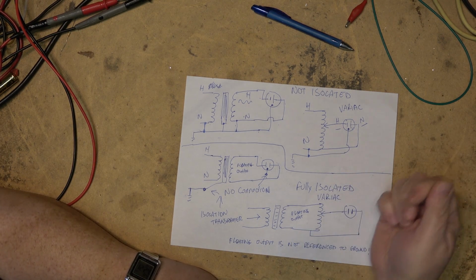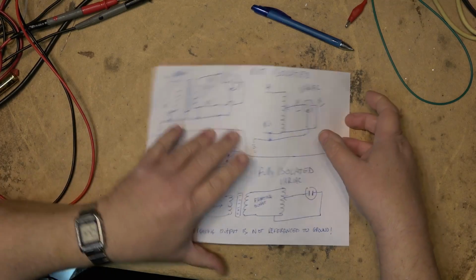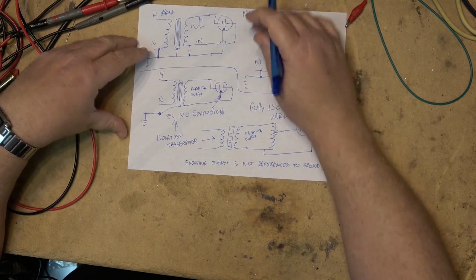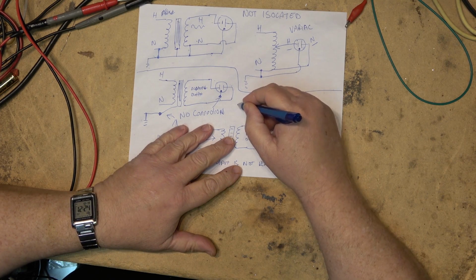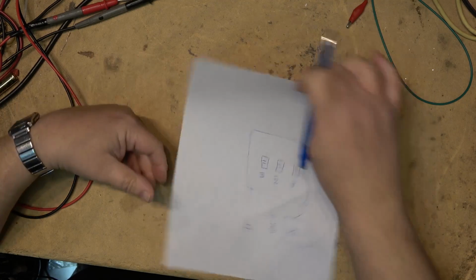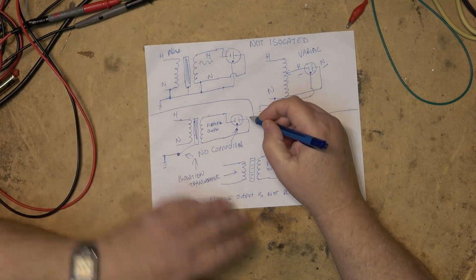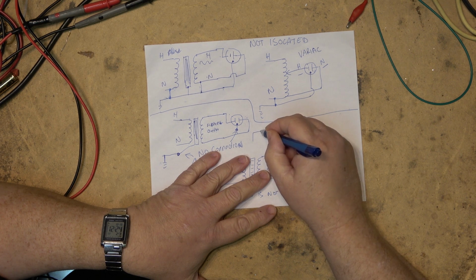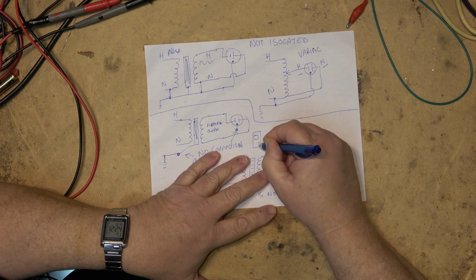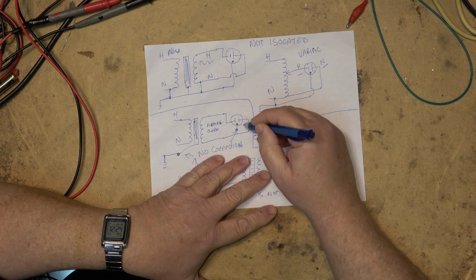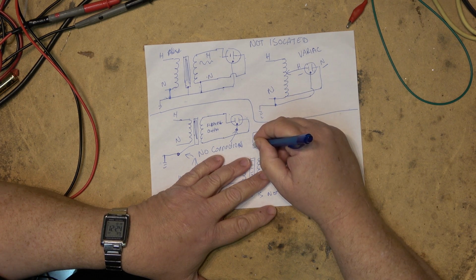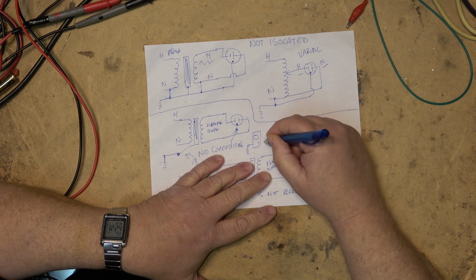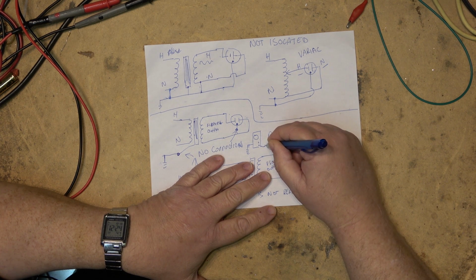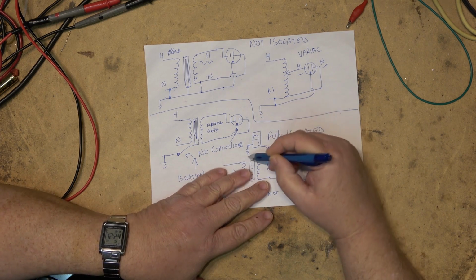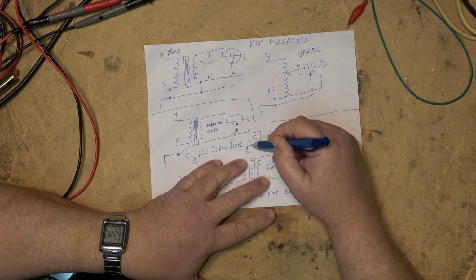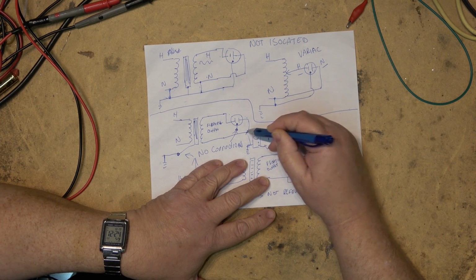Don't plug your test equipment into an outlet with a ground, because adding a ground, like if you've got your scope hooked up, for example. So you've got your product plugged in, and you've got your oscilloscope connected to the chassis, and your scope is grounded. I'll show you here. Even if your scope doesn't have a third prong, if it is plugged into a grounded outlet, your scope is grounded, right? And your chassis is connected to the ground on your probe, your little ground here. You've now restored, through that scope, a ground connection up to here, and you've now removed the isolation.